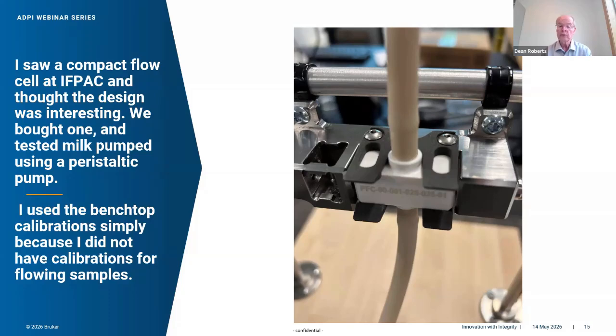And the nice thing about that is this little flow cell showing there in white is actually made out of polypropylene. And it's considered a single-use device where it's about $200 to put that in. And I bought one. And we put it in a peristaltic pump, closed cycle loop, and started running milk through it and making measurements. And I used the benchtop calibrations simply because I didn't have any calibrations that were developed on this flow cell. Next slide, Andy.